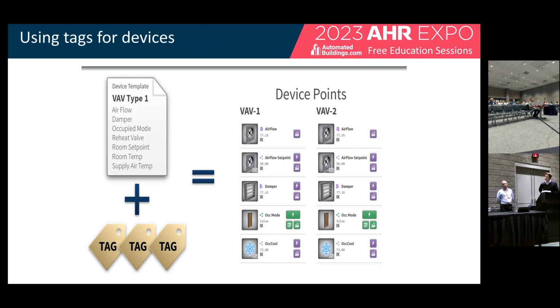If I was creating this graphic and wanted to teach a computer to do it for me, I would say to the computer, go look at where I'm focused. I'm focused on VAV1, read its points, and look at the tags on each one. If you see discharge, air, temp, and sensor, go grab a little icon that looks like a discharge sensor. Look for other tags, like do I have any history - there's a history tag on points as well - and if I do, put a little history icon next to it. And if it's a commandable point versus an input for a sensor, go ahead and put a little command icon right there. Those are all decisions I would have made as an application engineer engineering this graphic.